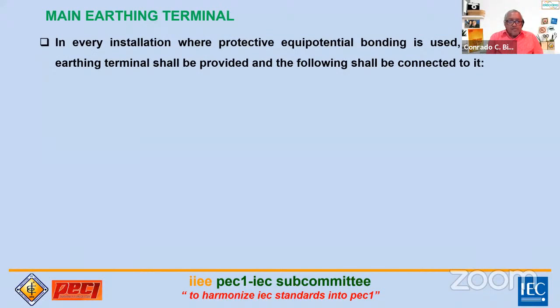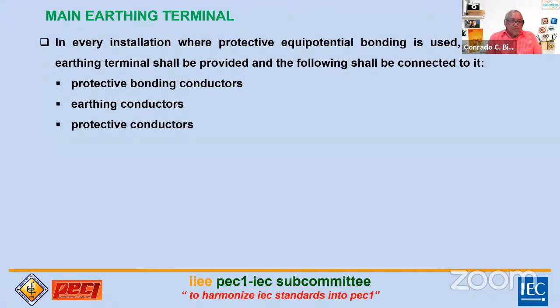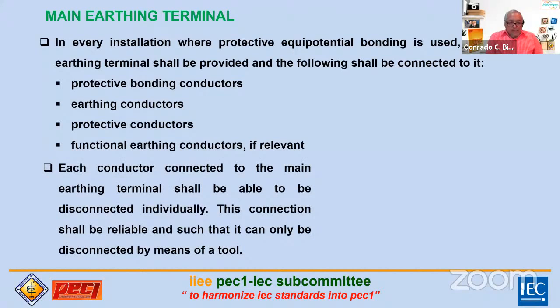So in every installation where protective equipotential bonding is used, ito yung main earthing terminal, yung MET, yung pinapakita natin kanina. This will provide the connection for protective bonding conductors, earthing conductors, protective conductors, and functional earthing conductors if relevant kung meron ka. Dito lahat i-connect, isang point lang sa installation. Then each conductor connected to the main earthing terminal shall be able to be disconnected individually. So this connection shall be reliable and such that it can only be disconnected by means of a tool.